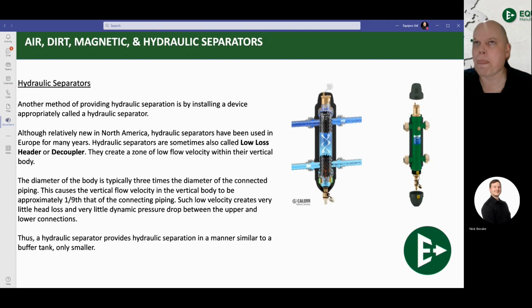If you have a whole home, a 2,000 square foot home with 5 different zones in it, you can see flow rates as little as 1 or 2 GPM, where the system flow is going to be much less than the boiler requires for its minimum flow. So a hydraulic separator separates everything nice and easy, protects the boiler always, and is an extremely simple install. It lets the boiler do what the boiler needs to do and the system do what the system needs to do. It doesn't matter what flow each one requires at the time.